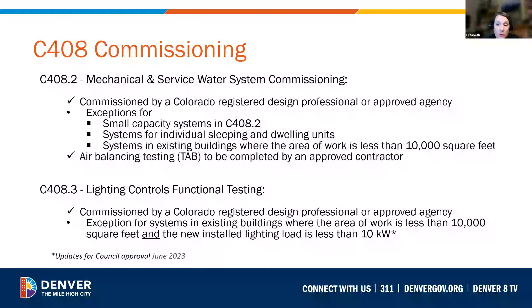Existing buildings undergoing a major equipment replacement of the same capacity thresholds of C408.2 will require commissioning when most of the devices directly connected to that equipment are also being replaced, such as in a complete floor demolition. And of course, commissioning must be done by a Colorado licensed professional or approved agency. The commissioning agent does need to be in place at the time of permit with qualifications noted on your checklist.